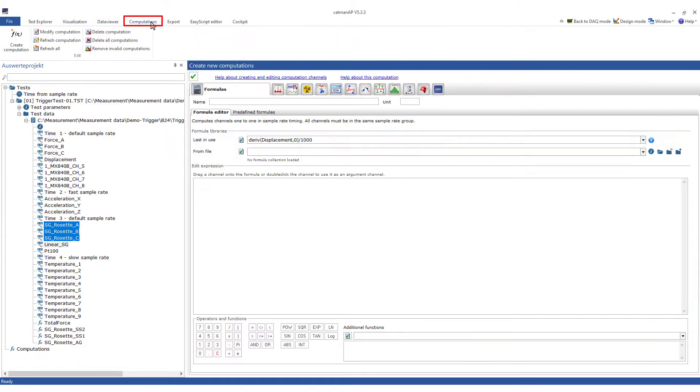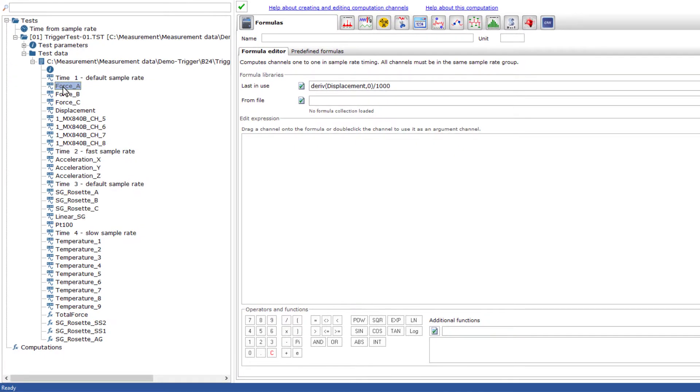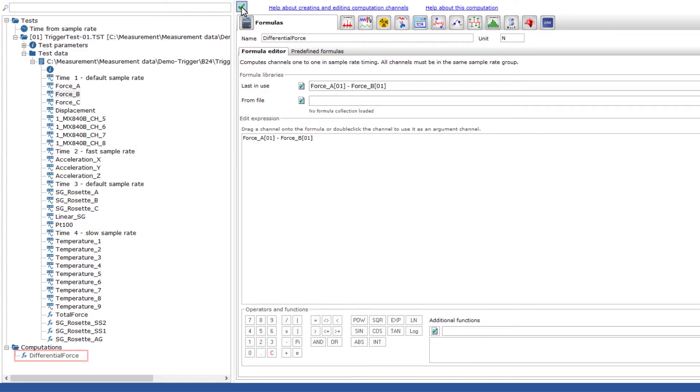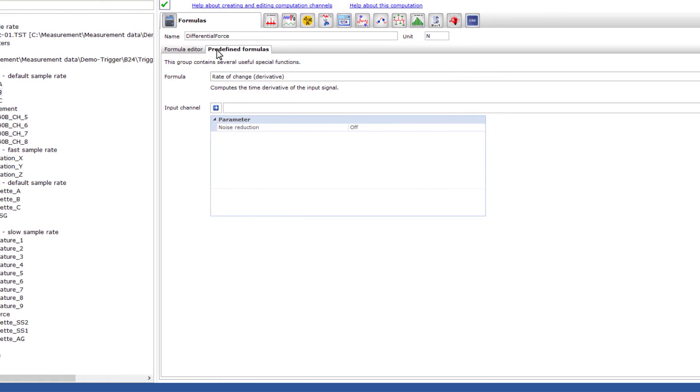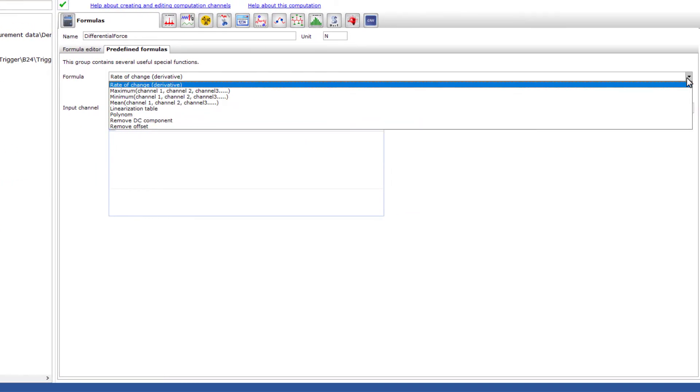In the computations, I'll now create calculation channels. The differential force between force A and B shall be calculated. The channels are calculated exactly as in the measurement mode in the formula editor. A name and a unit are assigned, and the calculation is created. Now I will do the zeroing of the linear strain gauge that I had forgotten about earlier.